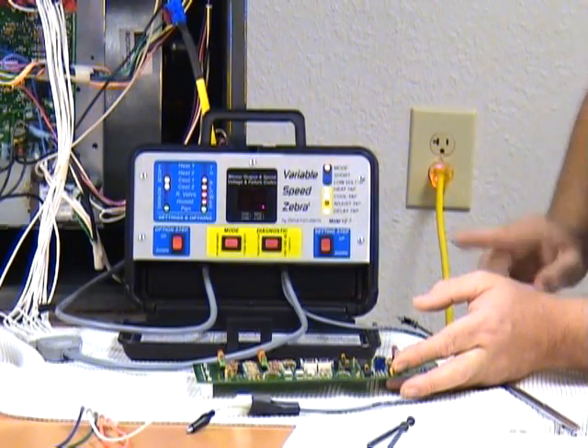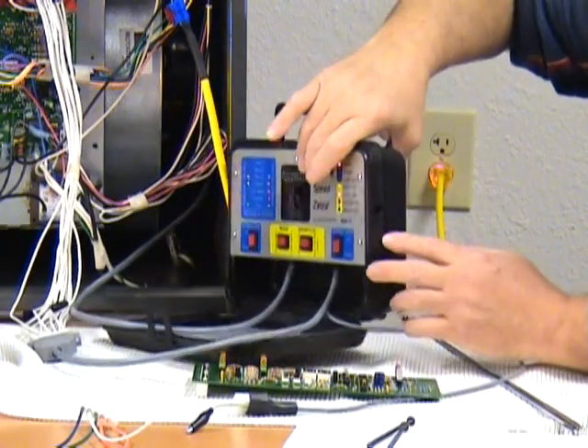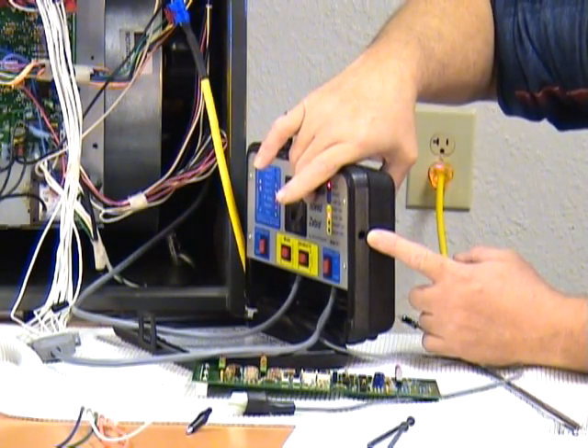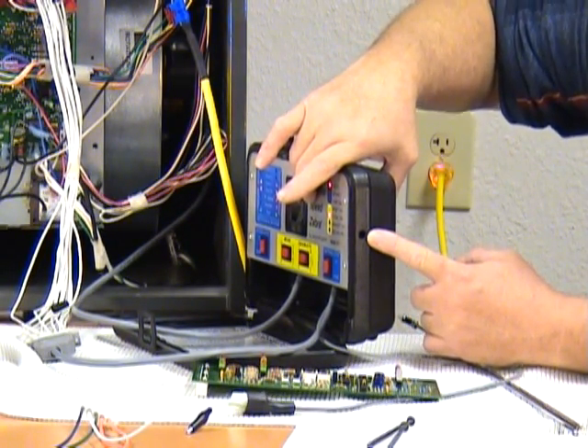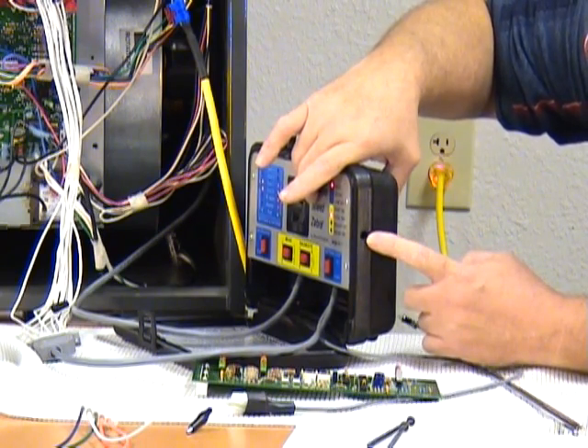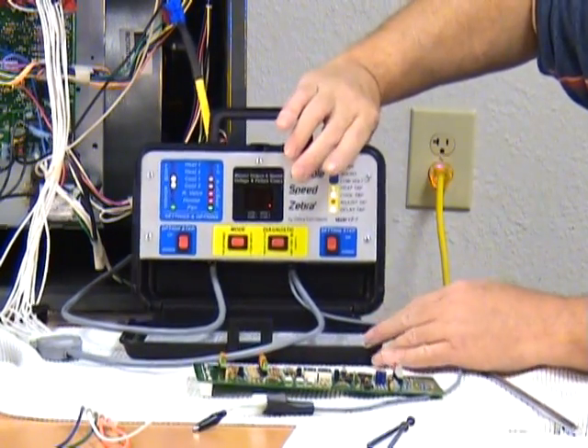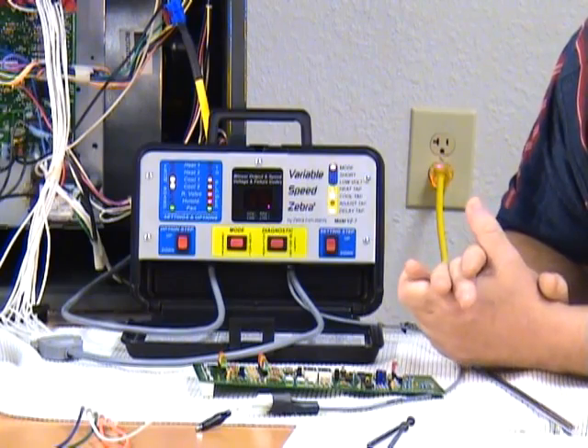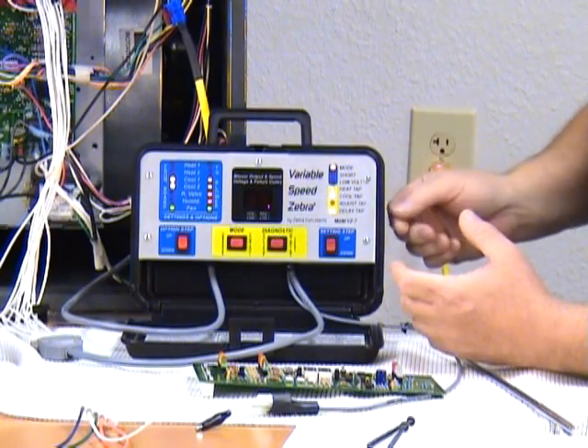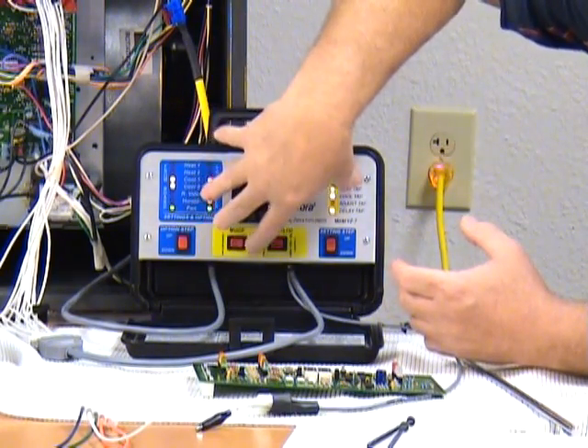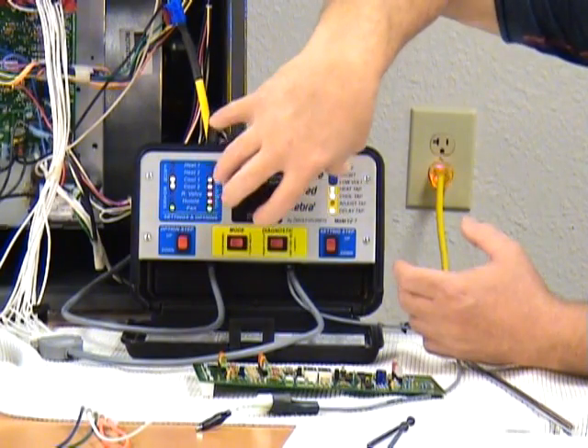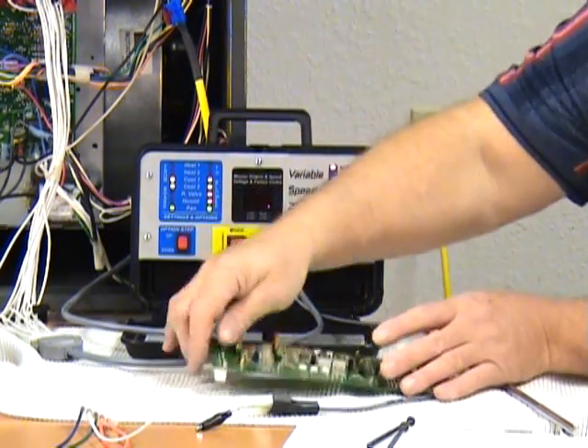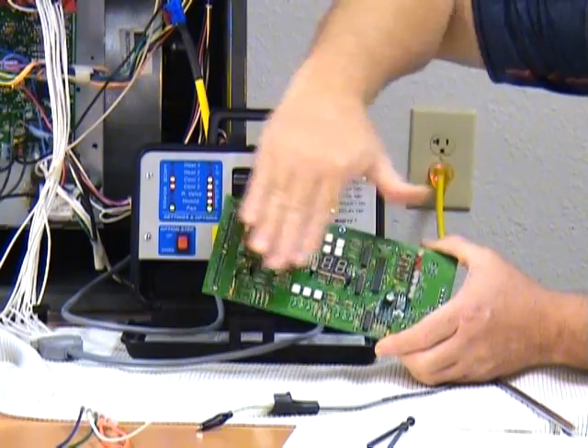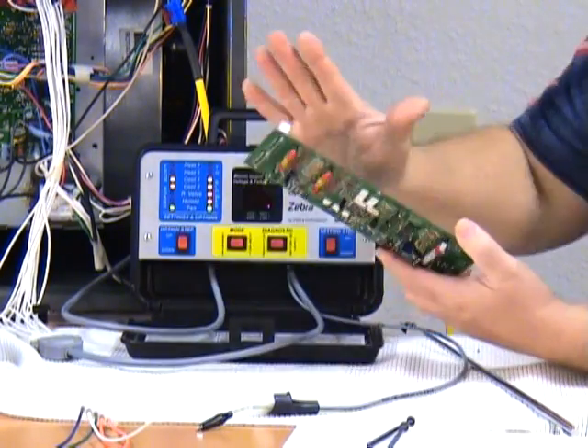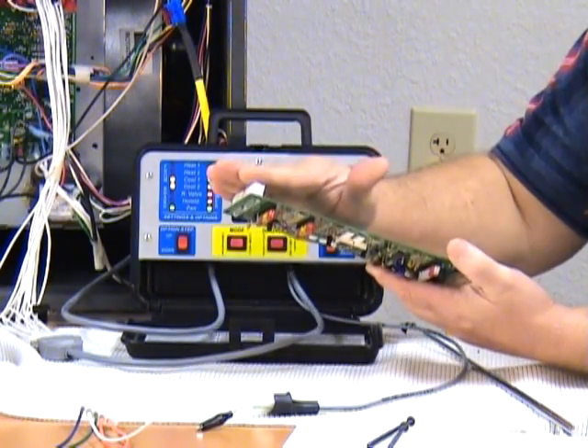You won't get it apart that way. There are 2 screw holes in the side of your variable speed zebra, one on this side, one on the opposite side, and recessed in there is a small Phillips head screw. And it's those screws that you use to disassemble the variable speed zebra. You take those 2 screws out and this whole assembly will come straight out this way. You cannot get to the front of this plate when you take it apart. The only thing you're going to be able to see is the back.